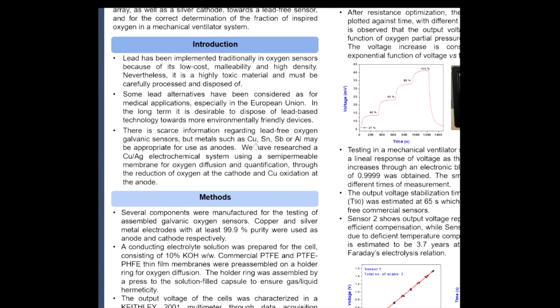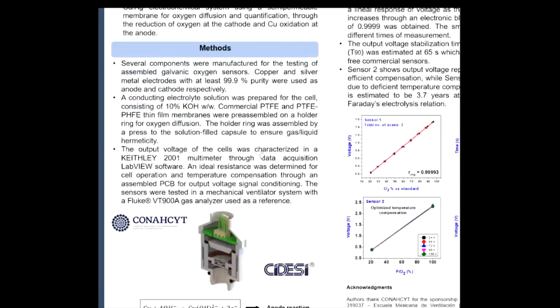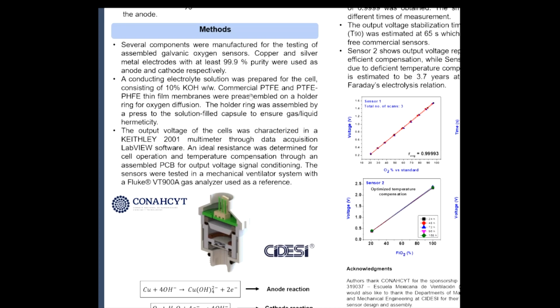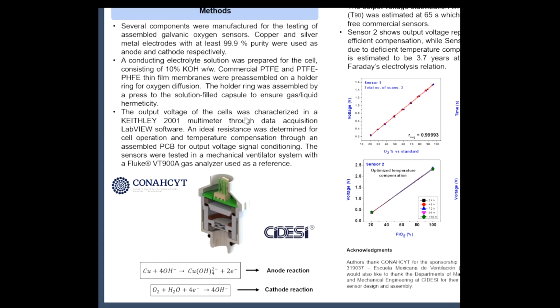Okay, so let's discuss the methods we used for this work. We manufactured several components for the testing of these assembled galvanic oxygen sensors, as shown here in the figure, where we use copper and silver metal electrodes with at least 99.9% purity, and these were used as anode and cathode respectively. We also prepared a conducting electrolytic solution with 10% potassium hydroxide, and we used commercial PTFE and PTFE-PHFE thin film membranes, which were pre-assembled on a holder ring for oxygen diffusion in the sensor.